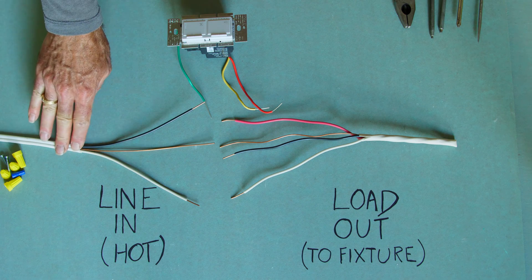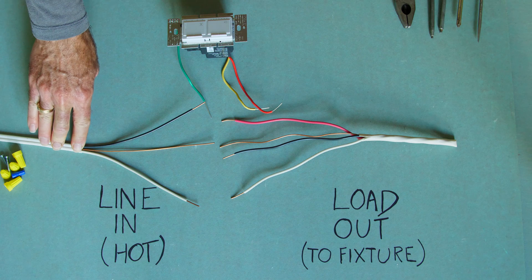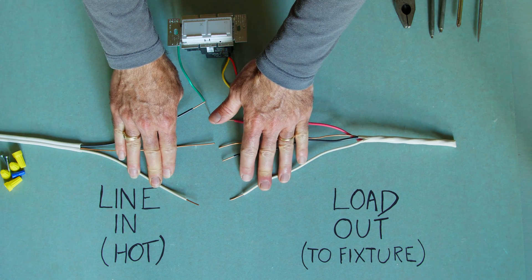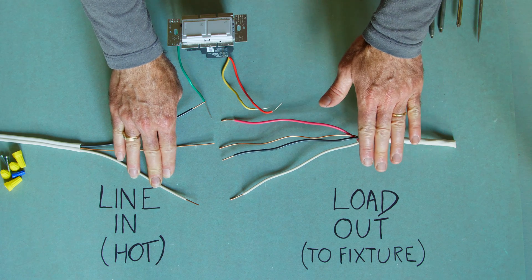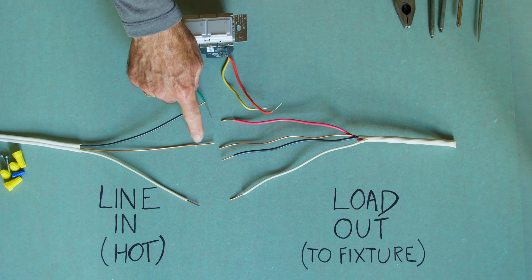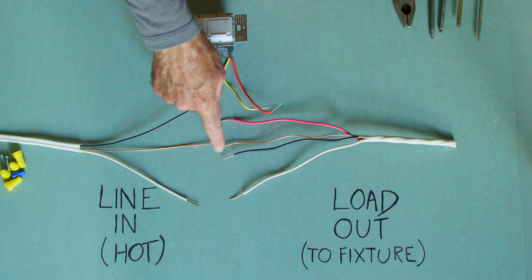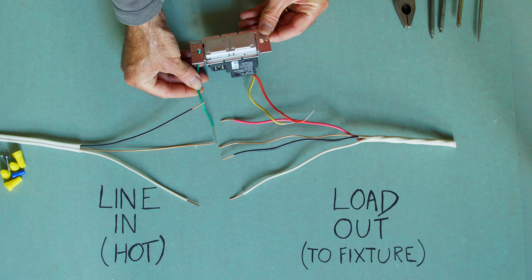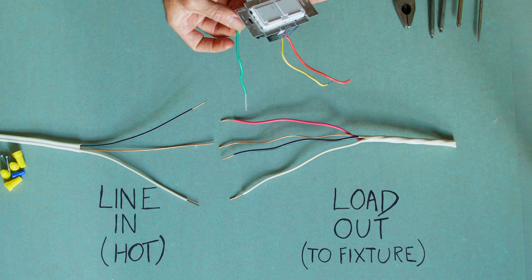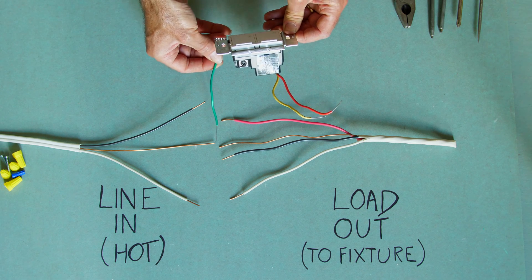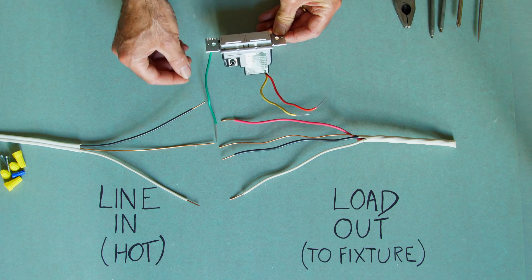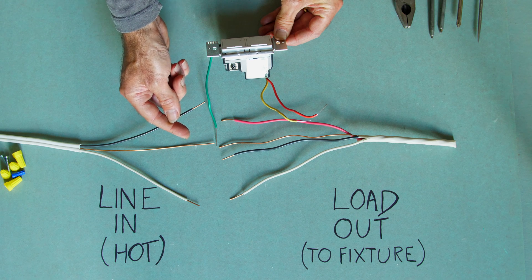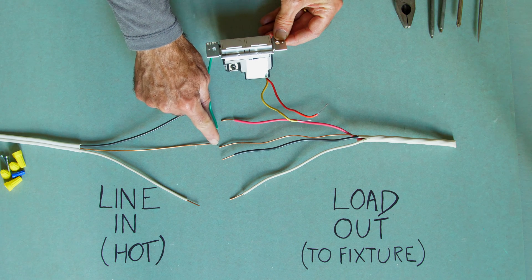Now starting with your line in which is your live wire, your power source, the white from your line in is going to go to the white of your loadout which is the one going to the fixture. Your bare copper wire which is your grounds will be connected together along with the green from the switch. If your switch doesn't have an existing green then make a pigtail and put that pigtail on as well, as there should be a ground coming from your junction box.